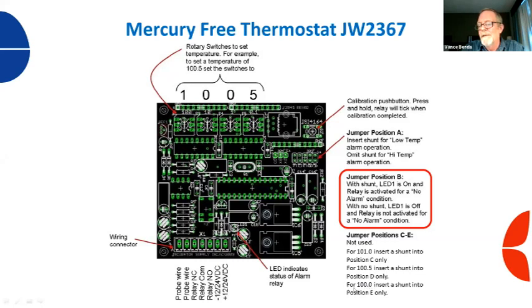Some people might use a 100 degree set point on multi-stage, but what we commonly use this for is calibration. So if you're doing a calibration on an incubator and you have this type of thermostat, you would move your shunt from C down and put it on E. Then we'd have to go down and tell the incubator to go to 100 degrees. And then we'd have to press the calibration button once our Electrotherm tells us that the machine has reached exactly 100 degrees. So calibration on these is a little tougher than calibration on this one, and we're going to talk about that in just a little bit.